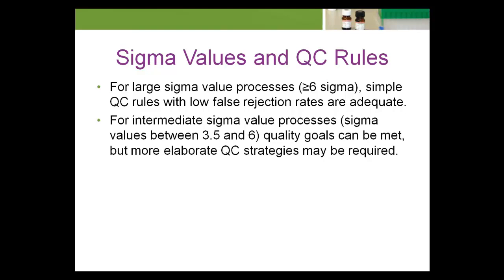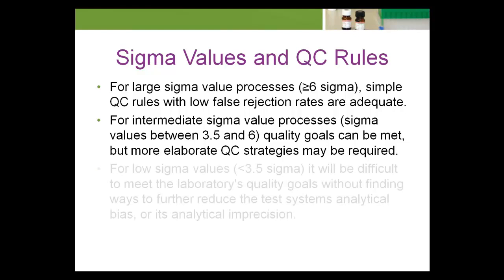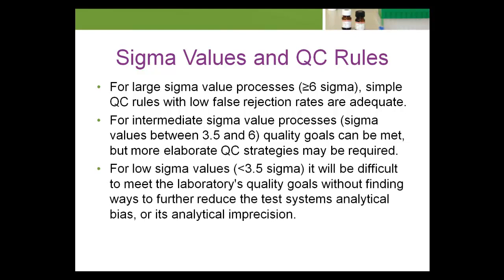For intermediate sigma value processes — sigma values between 3.5 and 6 — quality goals can be met, but more elaborate QC strategies may be required. For low sigma values less than 3.5, it will be difficult to meet the laboratory's quality goals without finding ways to further reduce the test system's analytical bias or its analytical imprecision.